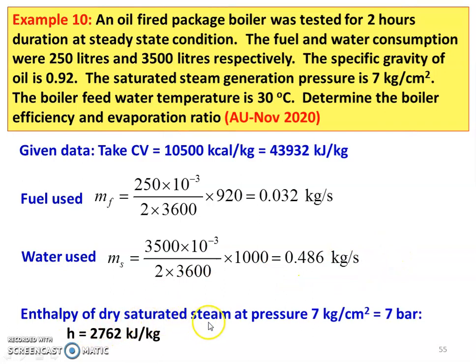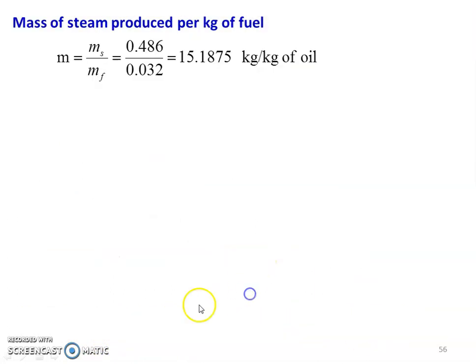Enthalpy of dry saturated steam at the given pressure of 7 kilograms per centimeter square, which is approximately equal to 7 bar, is 2762 kilojoules per kilogram from the steam table. Mass of the steam produced per kilogram of fuel: M equals MS divided by MF, which is 0.486 divided by 0.032, equal to 15.1875 kilograms per kilogram of oil.